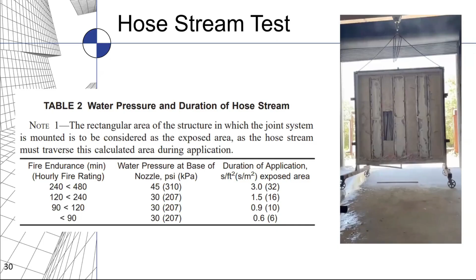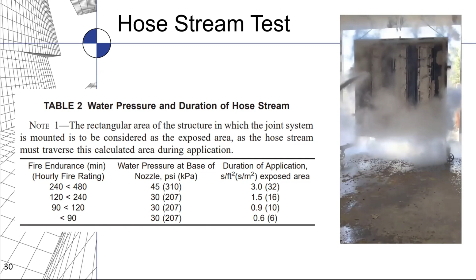After that's all done — in a penetration or a joint, in this case a gypsum wall apparatus — once the material has been fire tested, they remove it and spray it with a high pressure fire hose. If there's any visible water on the other side of the opening, the cold side, while they're spraying the hot side, that's a failure, which makes for a very tough test.